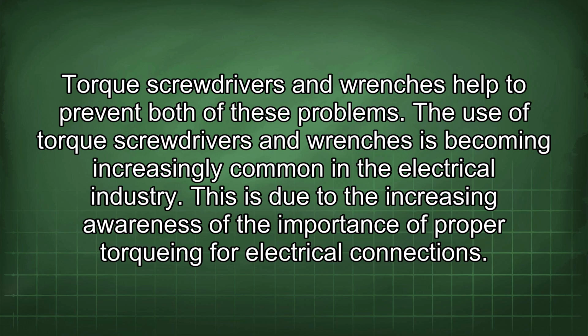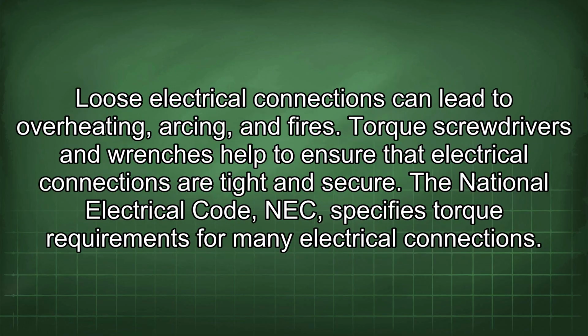The use of torque screwdrivers and wrenches is becoming increasingly common in the electrical industry. This is due to the increasing awareness of the importance of proper torquing for electrical connections. Loose electrical connections can lead to overheating, arcing, and fires. Torque screwdrivers and wrenches help to ensure that electrical connections are tight and secure. The National Electrical Code, NEC, specifies torque requirements for many electrical connections.